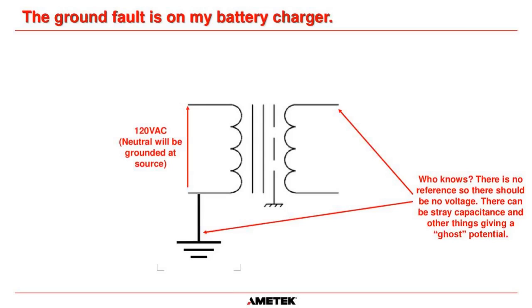How to find a ground which has a duration of 2 milliseconds and appears once per week or once every 2 weeks. Ooh, that is a tough one. Intermittent grounds are extremely difficult to find. If it's happening once per week, that tells me it's something on your load circuits. Something is happening on your load circuits once per week that is triggering a ground.